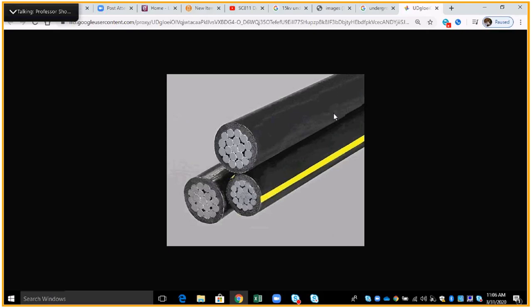You'll notice on secondary cable it's just like overhead cable with one difference. We have 120 volts here, that's our hot leg, 120 volts here, that's our other hot leg. And then we have a neutral. The neutral in overhead is not covered by insulation. In underground it is, and it's designated by the yellow stripe.